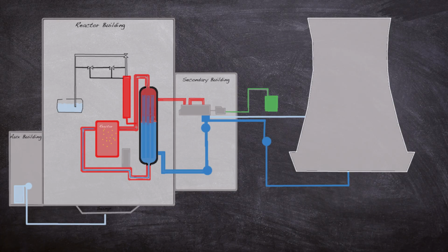To prevent overpressuring the pressurizer, a pilot relief valve is provided. If this valve is open to relieve pressure, steam and/or water flows into a drain tank. To prevent the tank from overfilling, a rupture disc is provided. For redundancy, an extra valve is provided in case the relief valve becomes stuck. This extra valve is called the block valve.